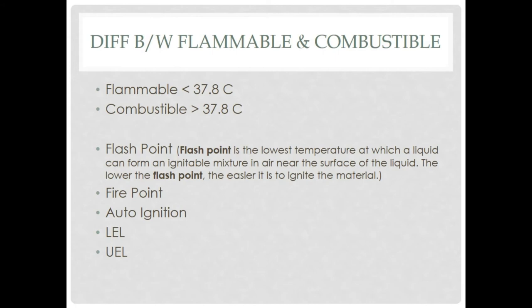Even with electrostatic charge or matches, if the gas concentration is above the UEL, it may not immediately ignite. But as soon as the door opens, fresh oxygen rushes inside, and the oxygen-gas mixture reaches the flammable range, creating an explosion or fire.